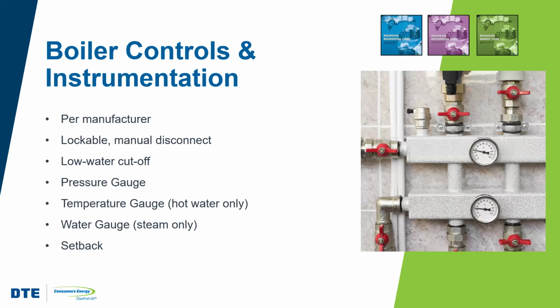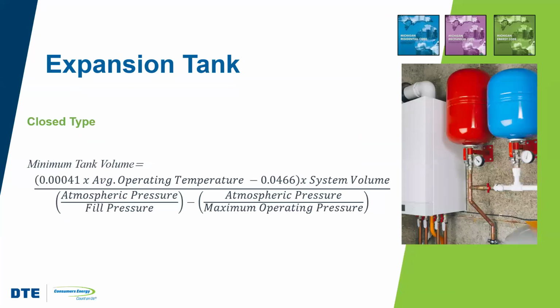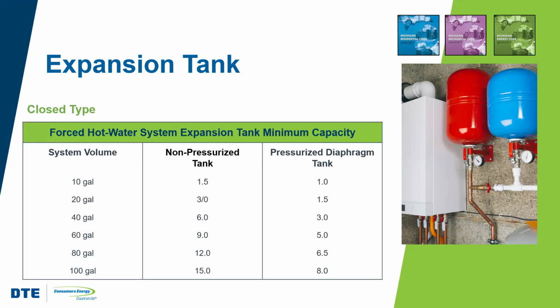You're going to have some temperature gauges, right, so that we know what the water temperature is inside the boiler system, so that the homeowner can know that this water temperature is in the right range. If the temperature gets too high, right, we can see that, and this also impacts the energy efficiency of the system. That expansion tank, we talked about this a little bit earlier. So for larger multifamily residential, where it would be considered a commercial application, there's a formula for determining what that minimum tank volume is going to be. On the residential side, there's just a really handy dandy table that tells you here's what your system volume is, and here's your minimum tank capacity, right? So that's a tabulated value.